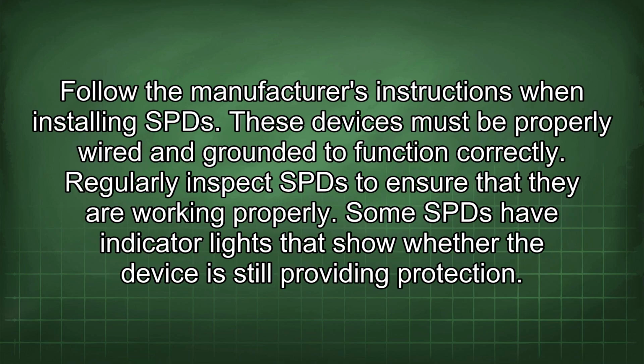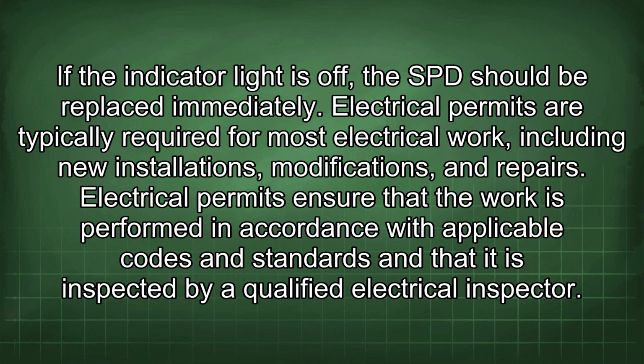Follow the manufacturer's instructions when installing SPDs. These devices must be properly wired and grounded to function correctly. Regularly inspect SPDs to ensure that they are working properly. Some SPDs have indicator lights that show whether the device is still providing protection. If the indicator light is off, the SPD should be replaced immediately.